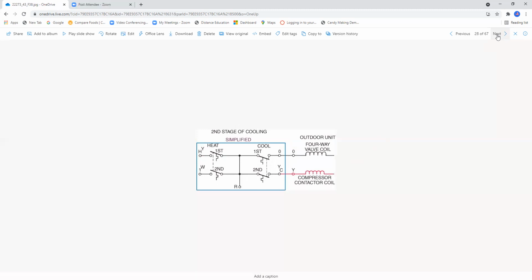Second stage of cooling. Take a look at that. Okay, second stage of cooling. This is also found in 1294. It'll show what happens in a rise in temperature. The first stage of the thermostat's already closed. The second stage closes and starts the compressor. Compressor was the last on and will be the first off. We covered this in the PowerPoint previously.